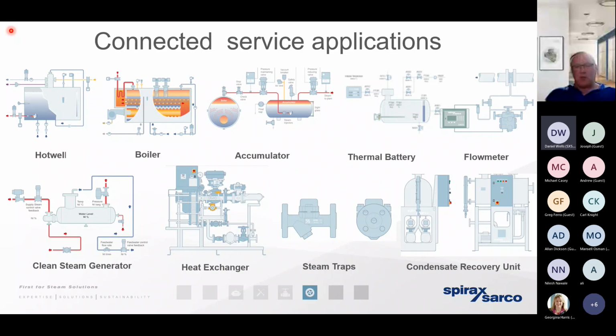Well, so far I've spoken about a lot of the products that have either just been commercialized or at a very advanced stage of commercialization. But it's critically important that we remember that key phrase, demand reduction. We could invest in all of the modern products and solutions I've spoken about, but if we're not observing good working practice in the operation and maintenance of our steam system, the effect is the same as investing in a very modern and efficient combi boiler at home and then going out and leaving the hot tap running all day. It's pointless. We need to remember the good working practice. And these are the things that we can do here and now to put our steam system in an excellent position for moving towards the next level in the coming months or years.